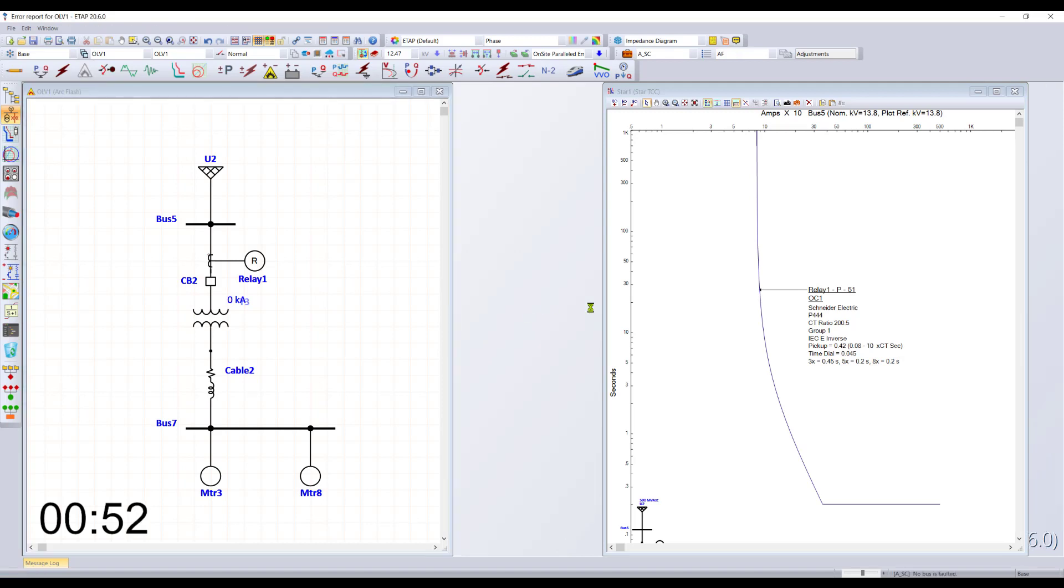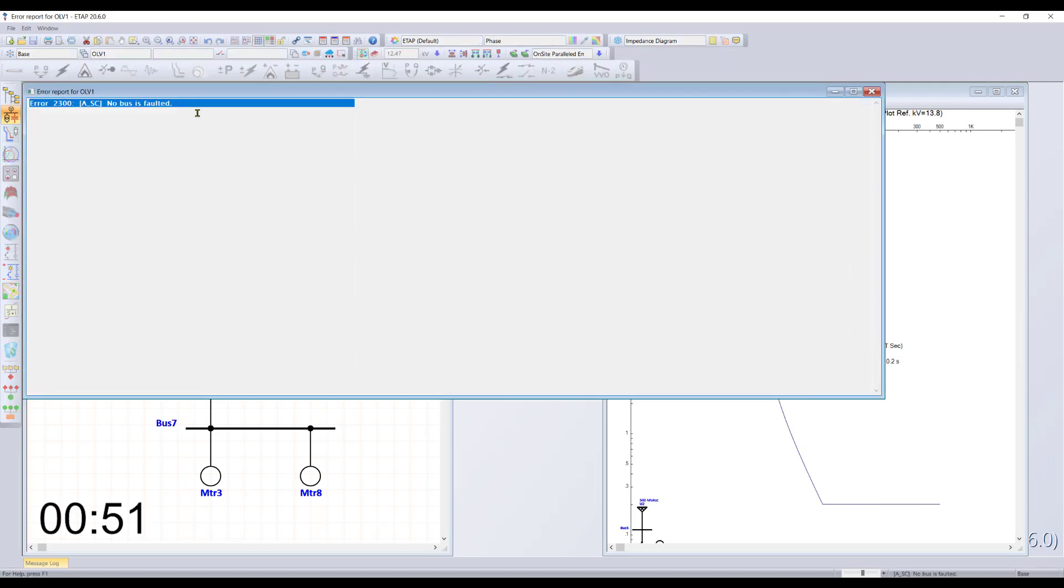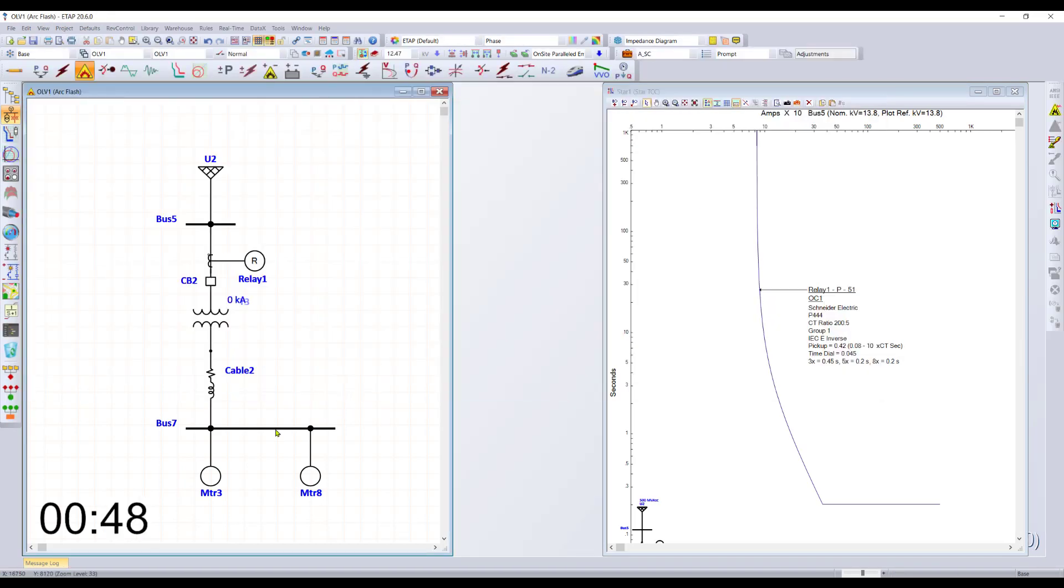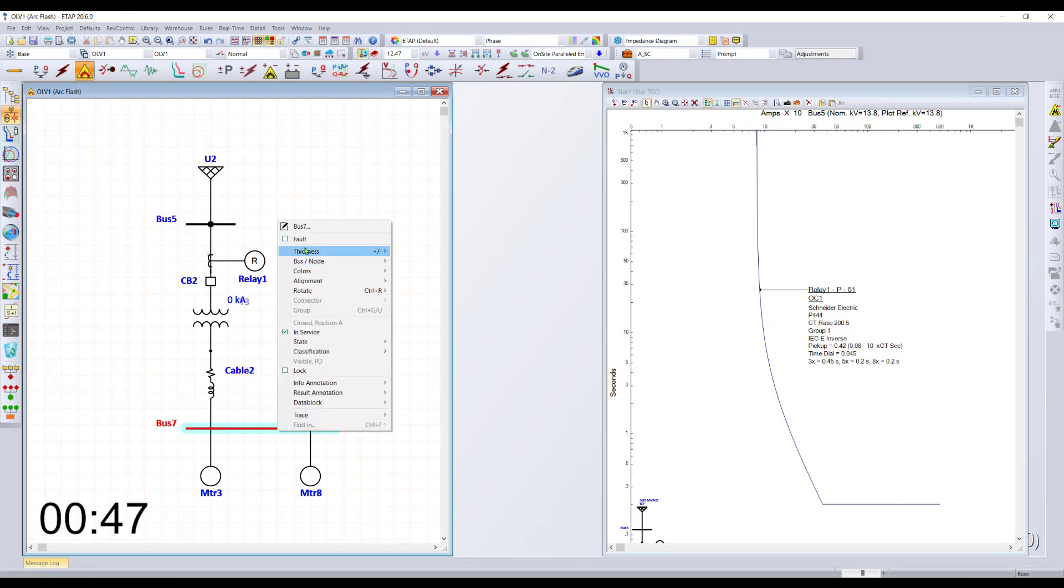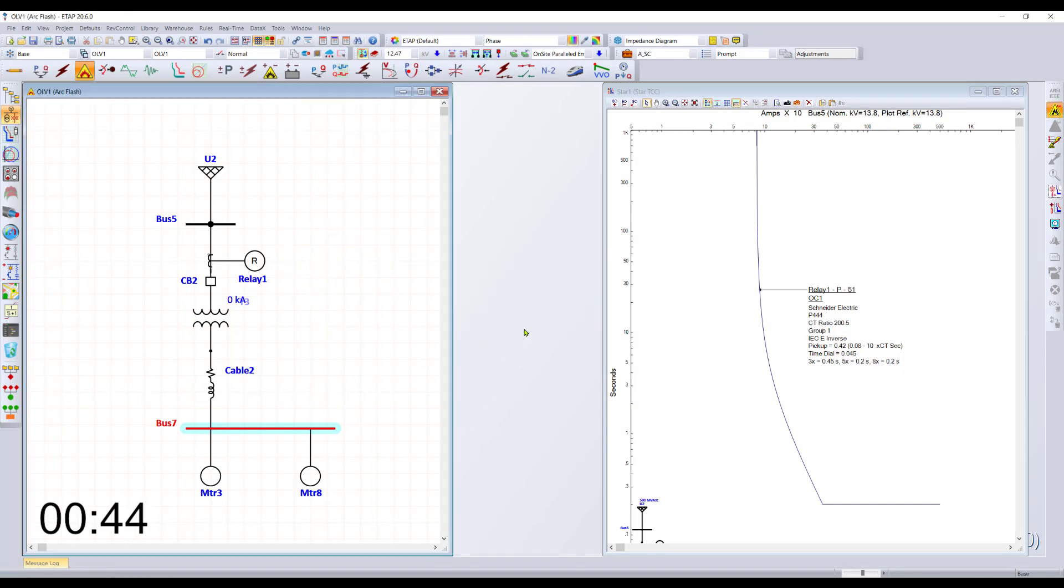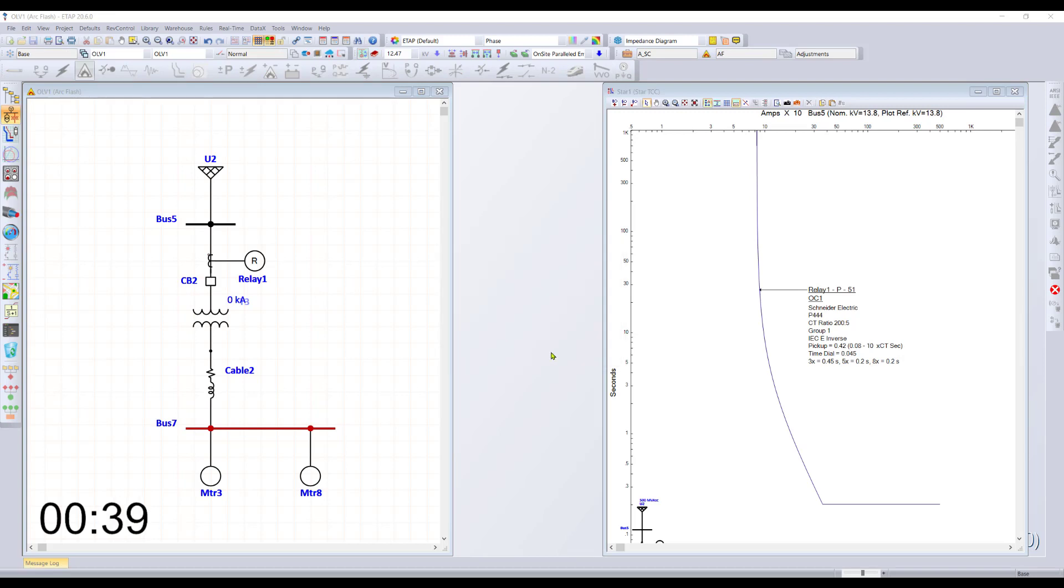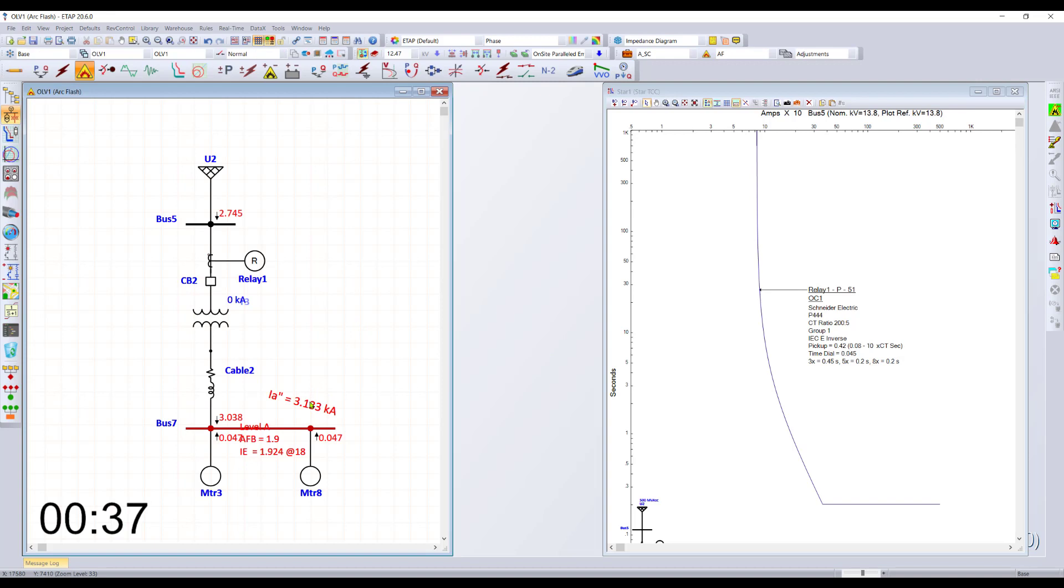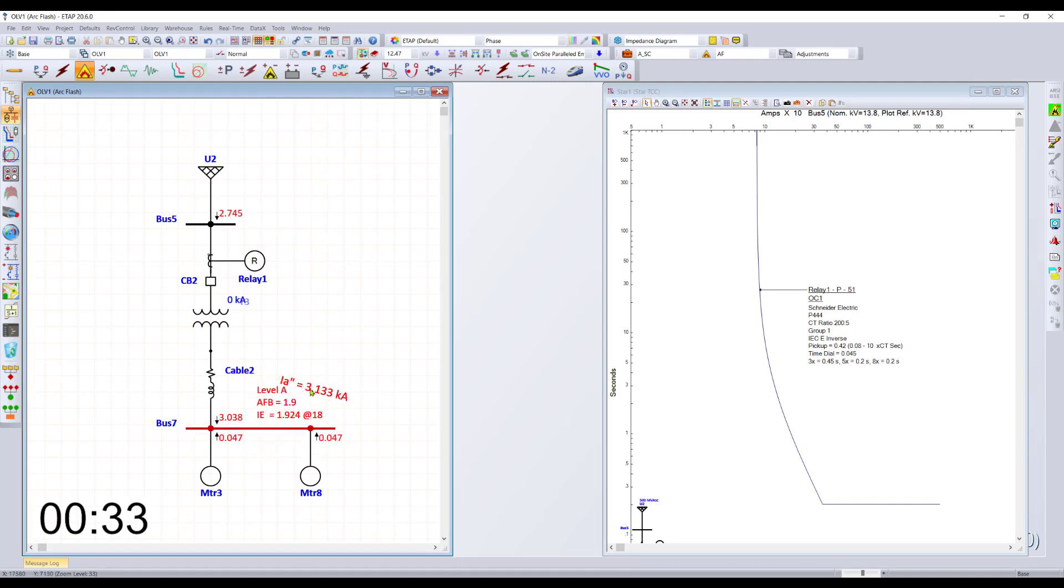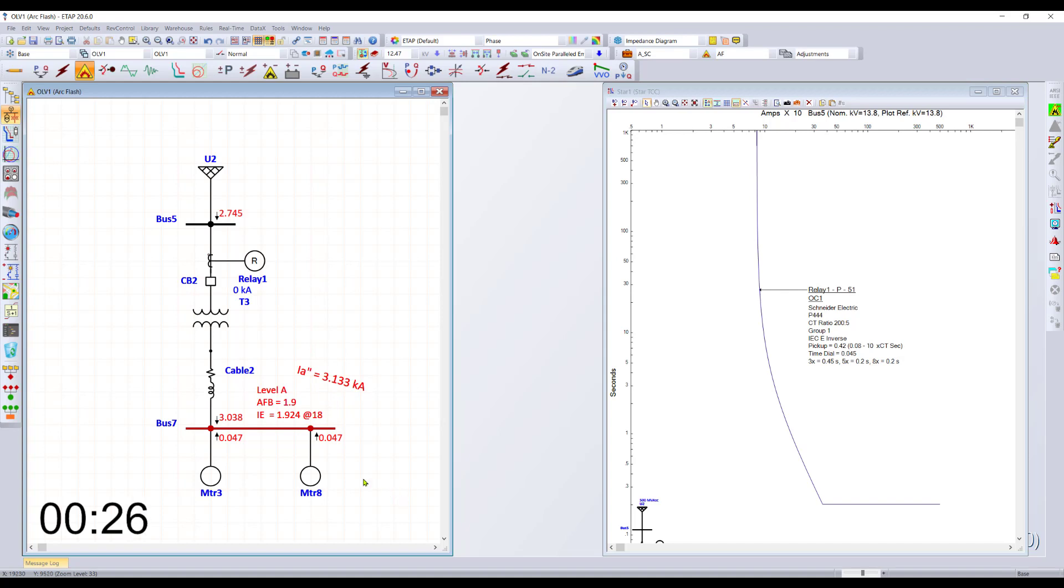Run our arc flash computation. We need to select a bus where we want to fault, so we can right click and fault. Run our arc flash study. The program gives a warning that the PPE requirements have not been approved, so it's essentially doing a safety check. Based on the current short circuit results and the relay setting in the network, we can see what the arcing current is as well as the arc flash energy.